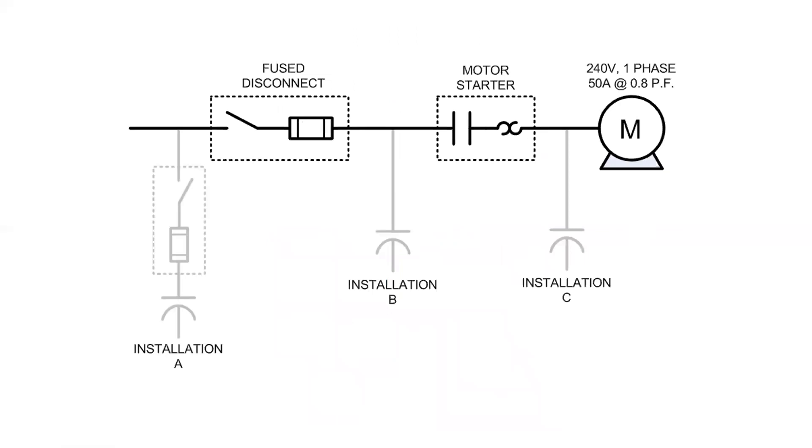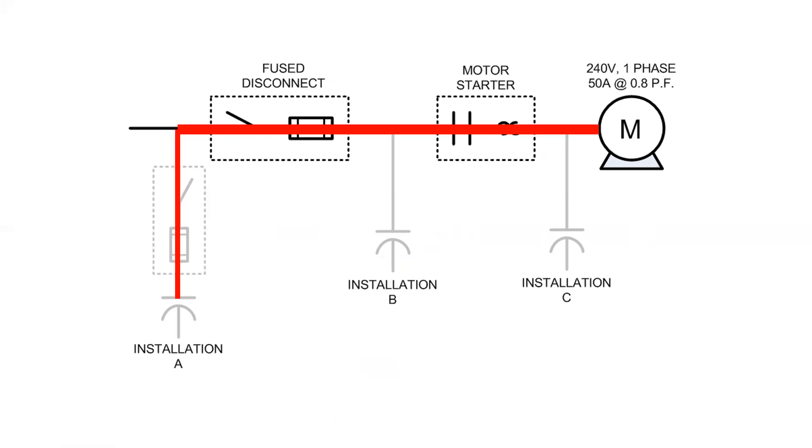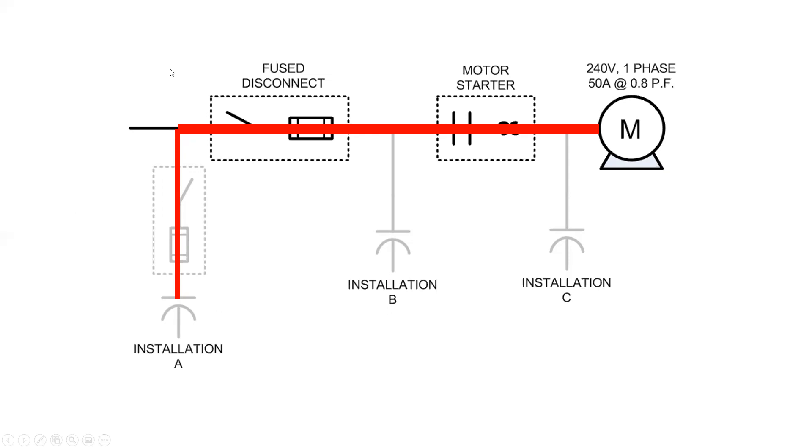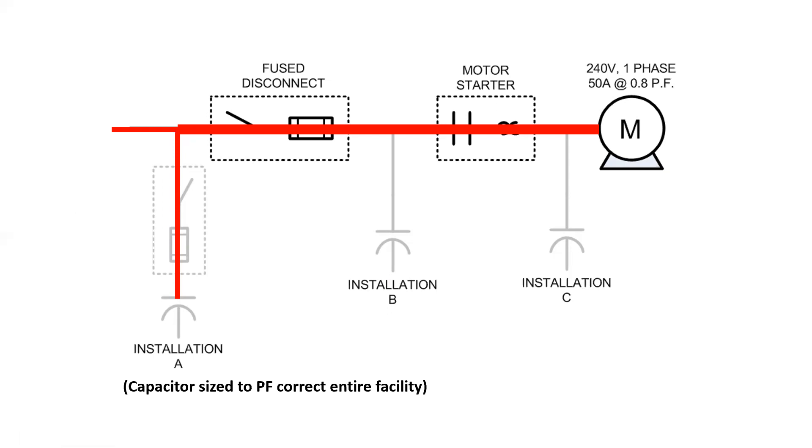So if we look at this particular installation where we have three different possibilities for where the capacitors could be installed, the first one here, installation A, is typically done where we're going to power factor correct more than just the motor. In this particular situation, we have our own over current disconnect, and it could also supply power factor correcting leading current upstream. So if this is the case, it means that all of the equipment from here down is all sized as per normal. There is nothing that needs to be oversized or undersized. It has absolutely no effect on the sizing. So this would be a capacitor sized to power factor correct the entire facility.